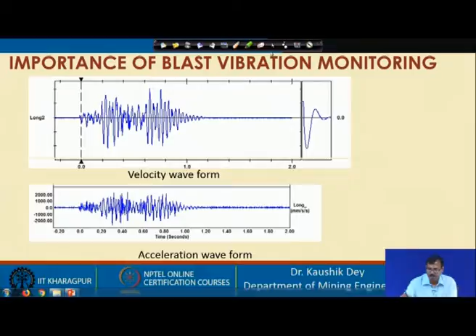That is why the acceleration measurement may sometimes be very useful for our purpose, and that is why it is judicious that any waveform measured, either on the velocity scale or the acceleration scale, has to be looked at in both scales at least once. So, this is in the same time scale, which is properly matched. You can see these zeros are coinciding. You can see the top velocity achieved may not be at a very high acceleration. So, it is not guaranteed that high acceleration means the velocity is also high. That is a very important thing that has to be considered while we are discussing this.